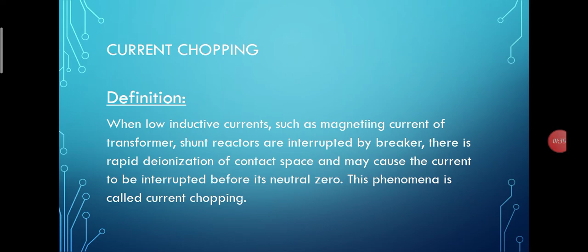In power lines, when a surge occurs due to lightning or switching operations at the time the circuit breaker opens, as in an air blast circuit breaker, when breaking low currents, that is unloaded transformer or reactor magnetizing current, the powerful deionizing effect of the air blast circuit breaker causes the current to go abruptly to zero well before the natural current zero is reached.